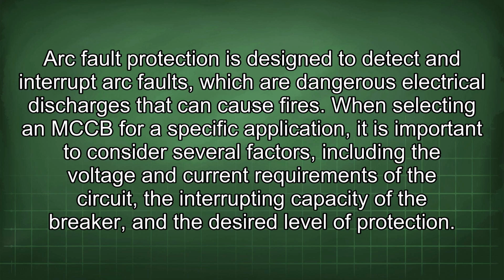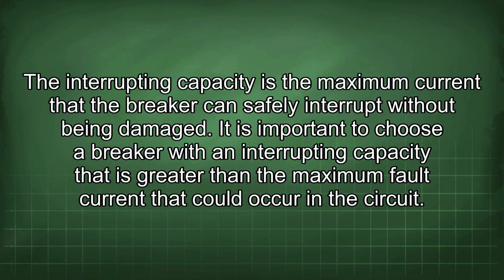fires. When selecting an MCCB for a specific application, it is important to consider several factors, including the voltage and current requirements of the circuit, the interrupting capacity of the breaker, and the desired level of protection. The interrupting capacity is the maximum current that the breaker can safely interrupt without being damaged. It is important to choose a breaker with an interrupting capacity that is greater than the maximum fault current that could occur in the circuit.